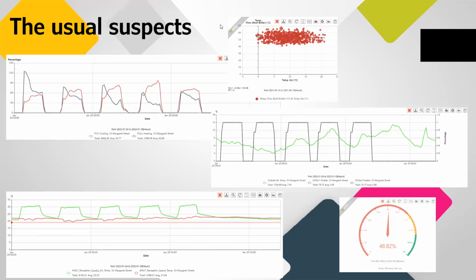Sometimes the BMS is set to provide a variable heating flow temperature into your heating system depending on the external temperature. But although these functionalities exist in the BMS, and the BMS was supposed to be set with that functionality, that doesn't happen in real life. So all these technical faults and issues are currently detected by AI, such as that we have developed for Watson, our metering, monitoring, and targeting and fault detection and diagnostic platform.